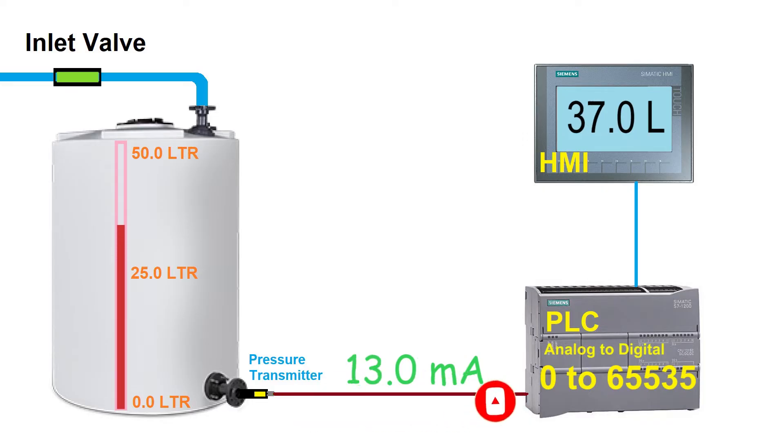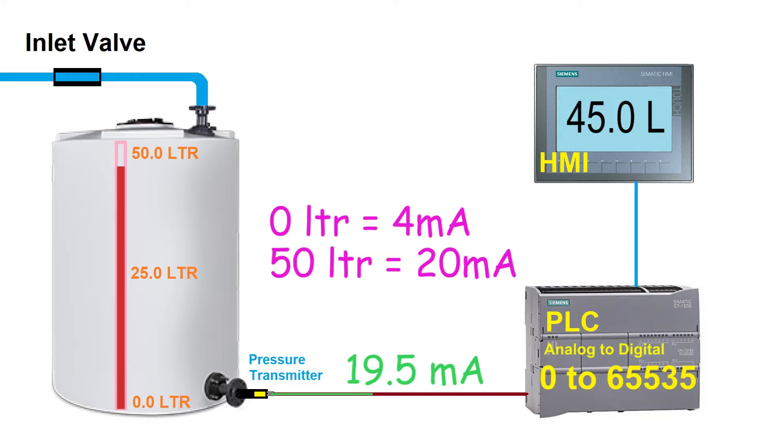As we start filling, the water level starts to go up and the level transmitter outputs 4 to 20 milliamps current signal to the PLC analog input. At 0 liters output current will be 4 milliamps and at 50 liters output current will be 20 milliamps.